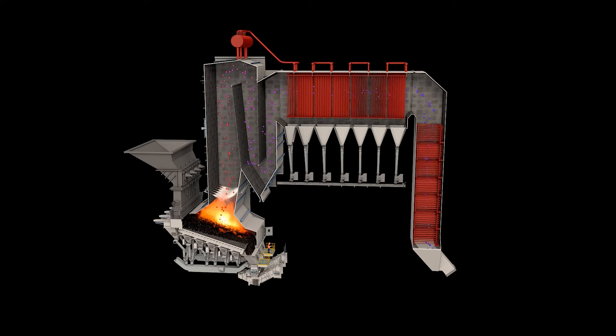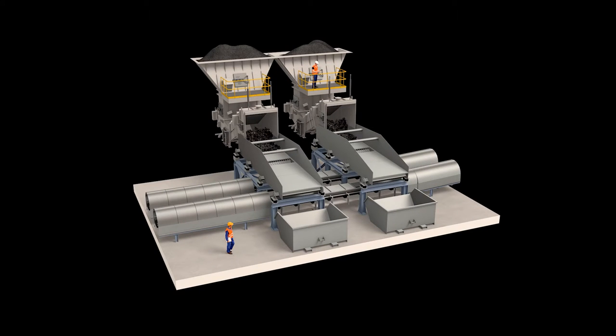Temperatures over 850 degrees for at least two seconds allow complete burning of the waste, which leads to low carbon values. Once combustion is complete, the inert ash that remains falls into the bottom ash extractor.